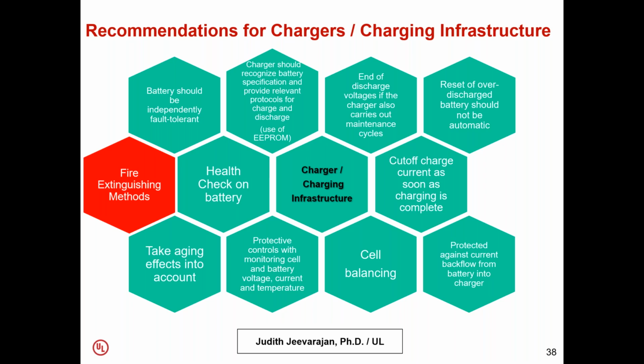Once the charge is complete, the charging current should be completely cut off - there should be no trickle charging. The health check of the battery should be performed before charging starts. Age of the battery should be taken into account, and the charger should also have additional protective controls for monitoring cell and battery voltage, current and temperature.